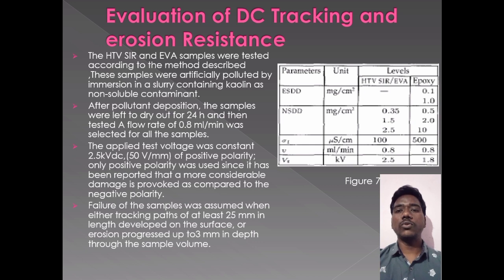The applied test voltage was constant at 2.5 kV DC of positive polarity. Only positive polarity was used since it has been reported that more considerable damage is provoked as compared to the negative polarity. A test duration of less than 8 hours was defined, except for those samples that failed before the prescribed time.